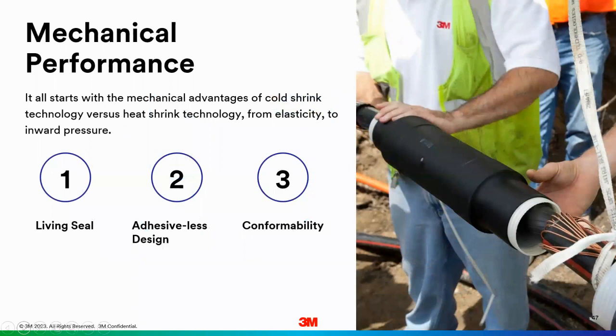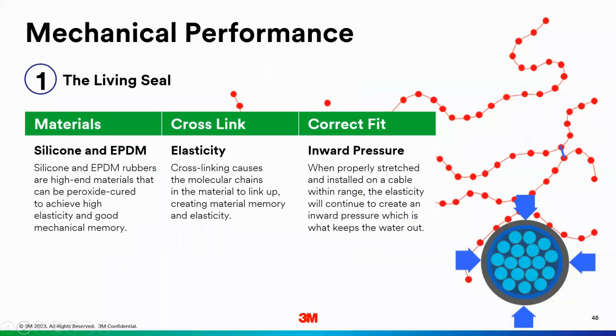So when comparing cold shrink versus heat shrink, it comes down to three main things: the living seal, the adhesiveless design, and conformability. When talking about the living seal, if you can see in the bottom right-hand portion of your screen, and this would probably be a little better in person, whenever you apply your cold shrink tubing, that tube is always trying to get to the smallest size, basically the size that it was before it was expanded and placed onto a core. So it has this living seal that's basically always applying inward pressure onto the cable.